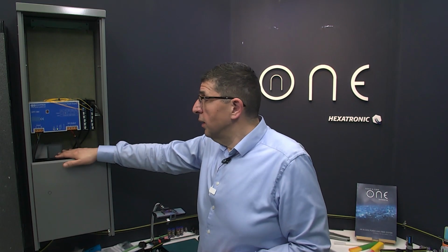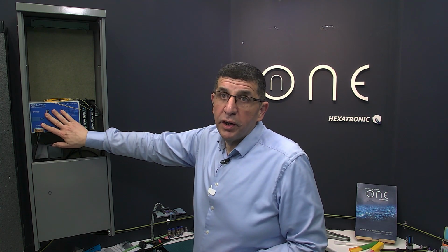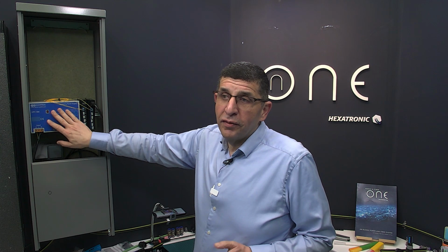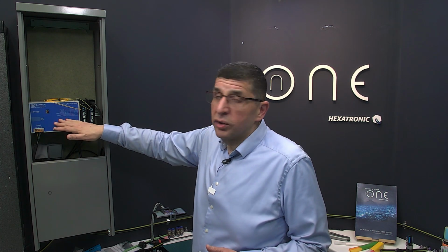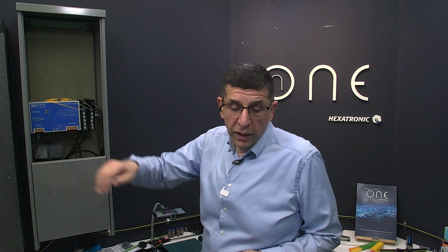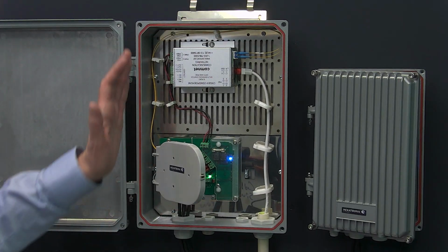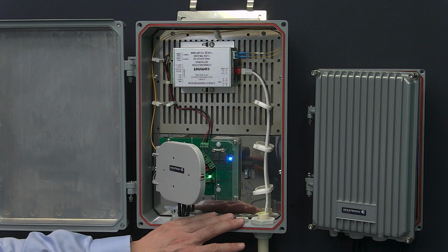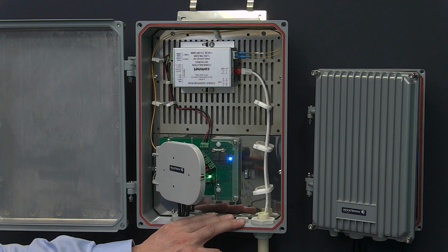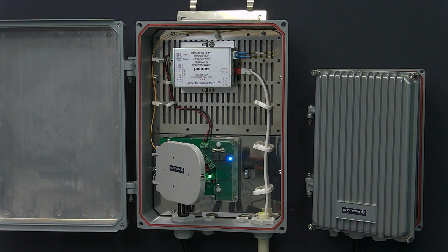Then there's redundancy against power failure, which is the interesting part. If I move to this one, you can put the UPS at this point, and everything connected to this cabinet, whether you have 2 or 10, will be connected. If installed inside your data center, you need an indoor UPS, whereas traditional solutions use a much bigger cabinet and put the UPS outside in a street cabinet, which is more expensive because it has to be rated for the external environment, needing fans and active ventilation. So this is the redundancy with the UPSs.